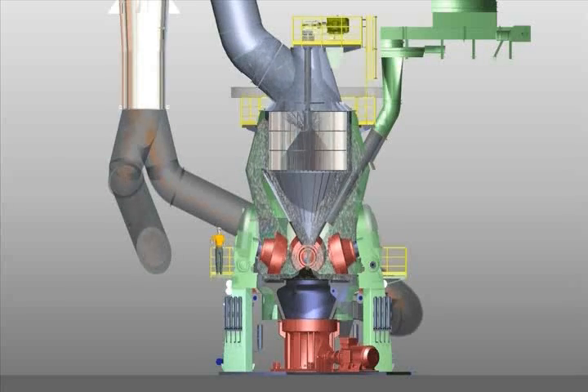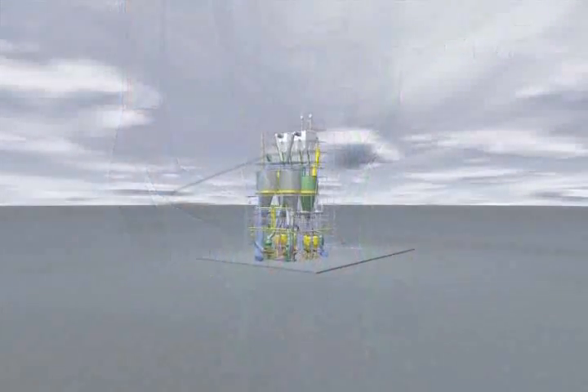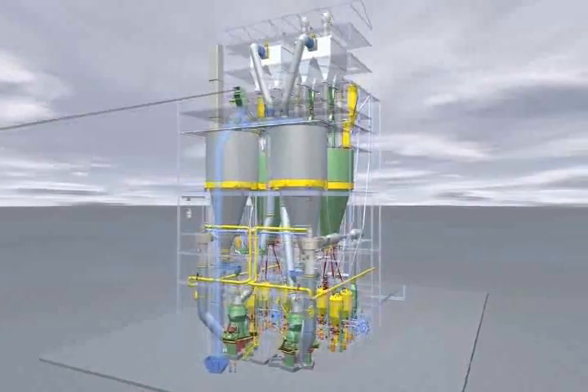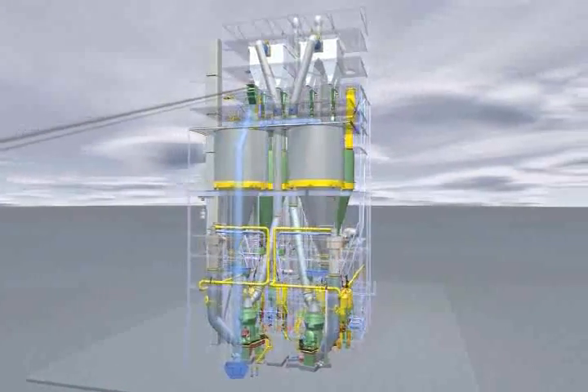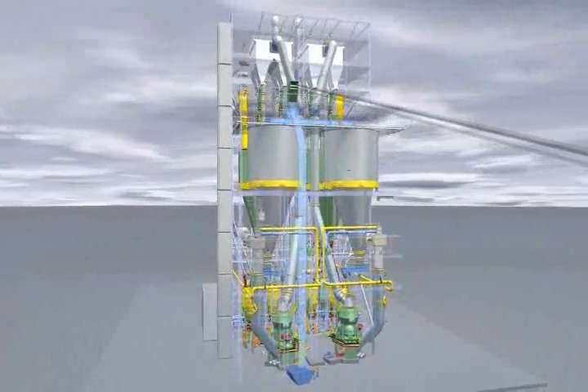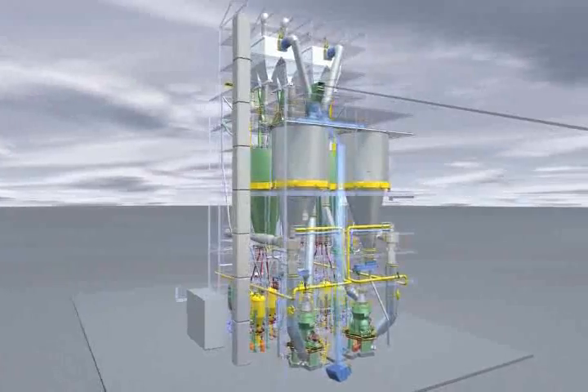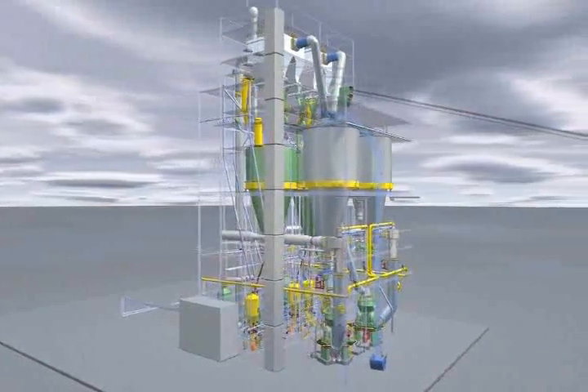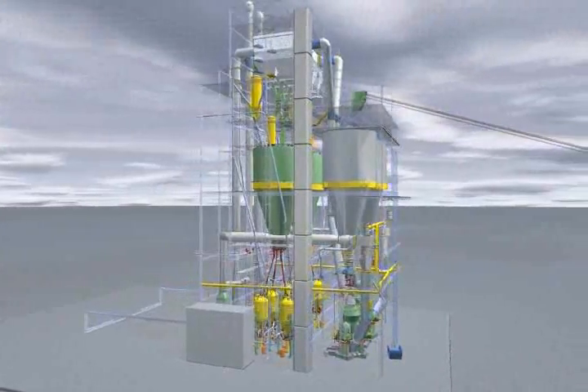The coal grinding plant is shut down gradually according to a prescribed shutdown sequence. All carbon monoxide analysis equipment must remain active during a standstill. Here you can see a two-line coal grinding plant that produces coal dust for use in the steel and iron industry, which has the same structure as a self-inert central coal grinding plant. If the plant is to be used in the branches of industry mentioned in the introduction, certain plant components are adjusted to meet the specific requirements of those sectors.